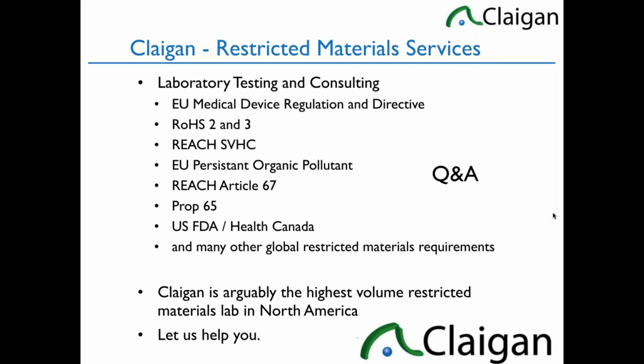What is the particular test that is done to show if your device contains a CMR or endocrine disruptor? That's a fantastic question. The way we do it, like we do for each SVHC, is a risk-based approach, which is what they recommend. We look at the material and what CMRs or endocrine disruptors could possibly be in there. Our lab also has screening techniques where we can screen out the common ones or screen them in. Depending on the material, there are different tests. It is not one test. The different CMRs have different approaches.